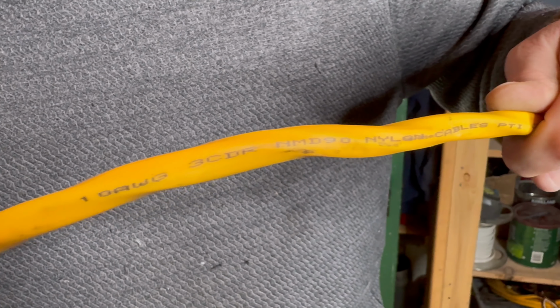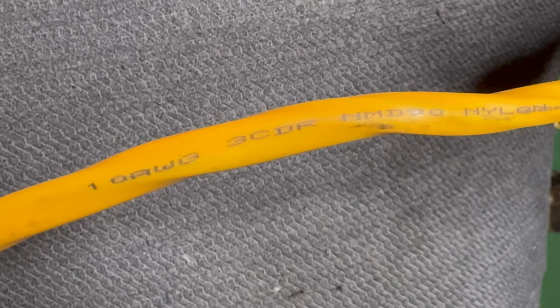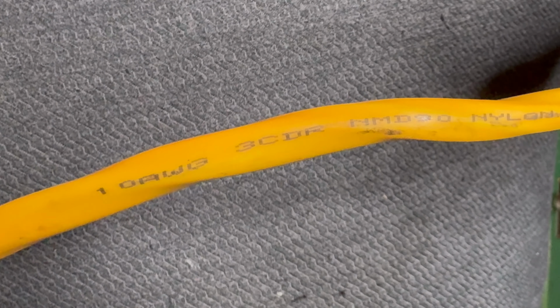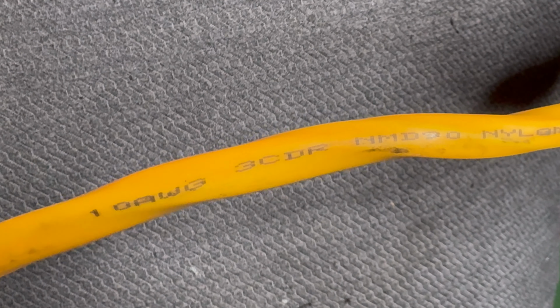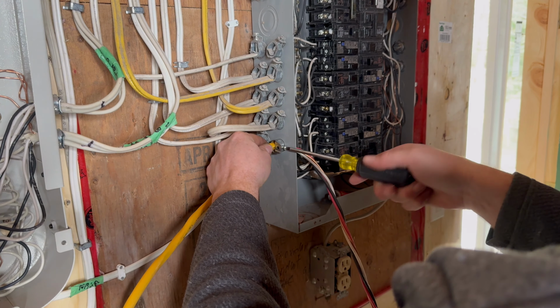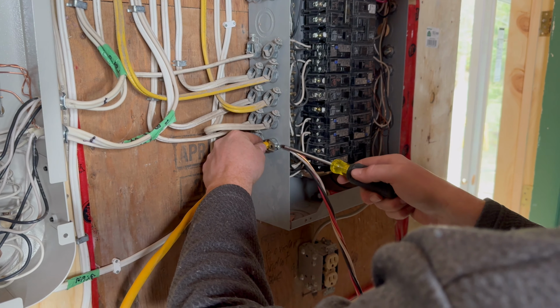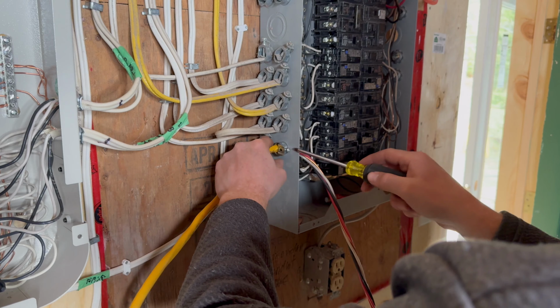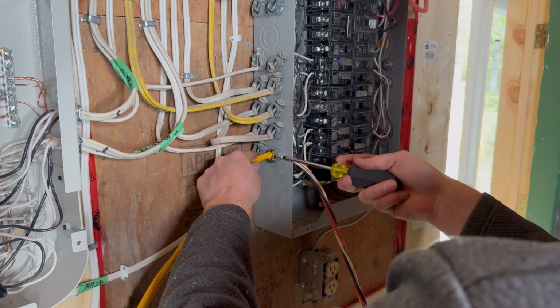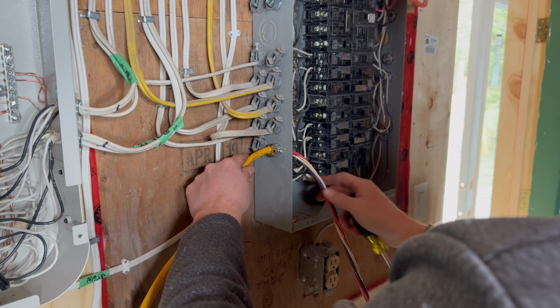Now, since we're dealing with a 30 amp transfer switch, we're using number 10 cable and a 30 amp breaker in the main panel. If you were installing the 50 amp model, you need heavier cable and an appropriate 50 amp breaker in the main panel.